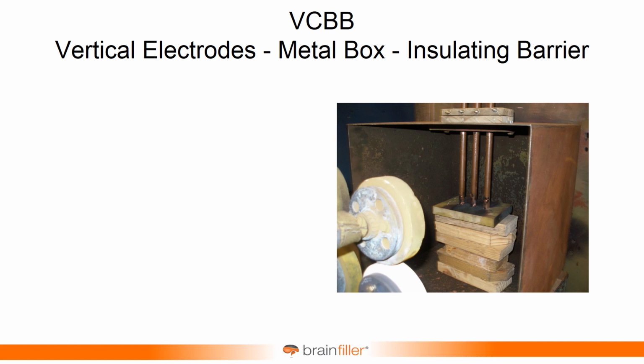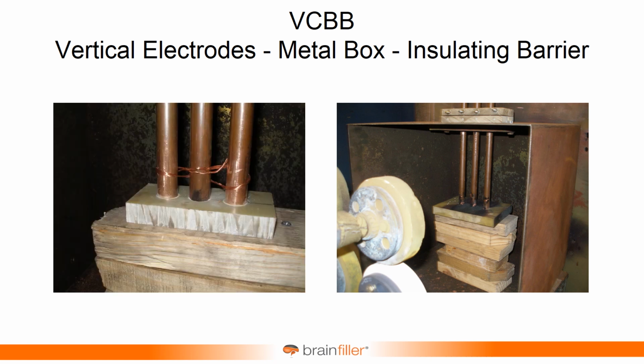And so what happened is there was this thought about what if the conductors terminated into an insulating barrier. And this is representative of certain conditions in some types of equipment. And the thought was the arc energy would be running down the bus, and it would hit that barrier, and it would balloon out and basically come out a little more aggressively. And so on the left side, I show the trigger, the fuse wire wrapped around it, and then it's a fiberglass block pushed up with a couple of pieces of wood, 2x4s. And so that's the setup.